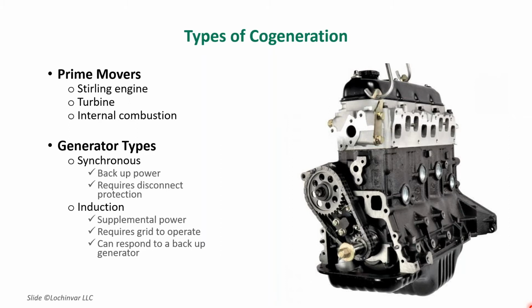It requires the grid to operate—if the grid goes down, we go down. Power companies really like this feature because there's no chance of backfeeding during a power outage. At the same time, if the facility already has a backup generator, say it's a hotel, it will read that generator as the grid, sync with it, and essentially throttle back that generator, reducing the wear on it.